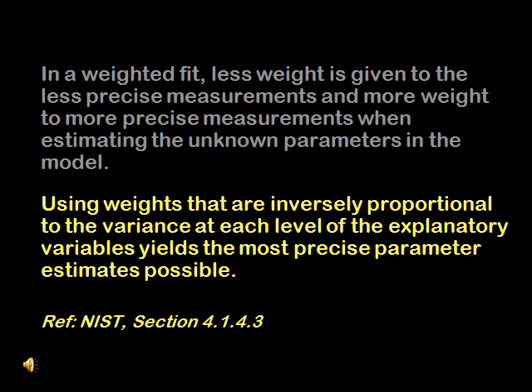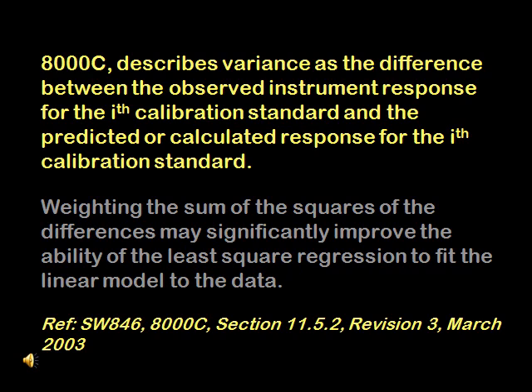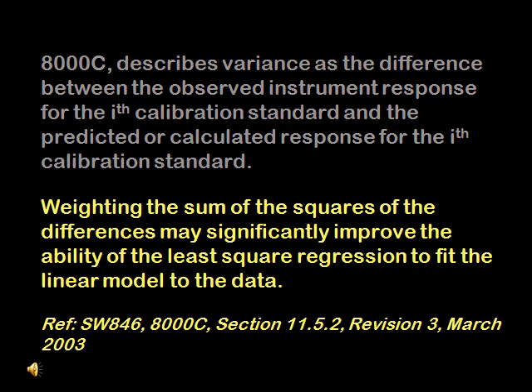The term variance is explained in the next slide. 8000C describes variance as the difference between the observed instrument response for a calibration standard and the predicted or calculated response for that calibration standard. 8000C continues that weighting the sum of the squares of the differences facilitates the data points to fit better to a linear model. The decision as to when to use weighted or unweighted regression is based on the error structure of the calibration.